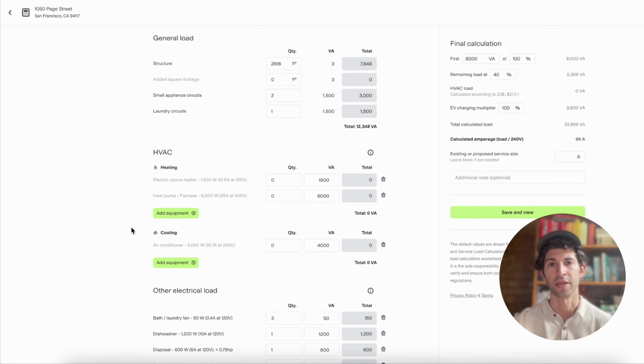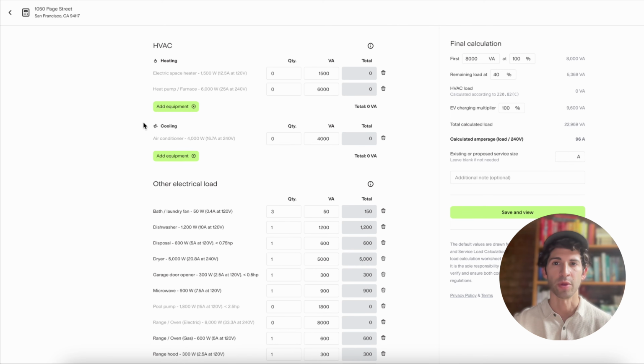Next, we can add in heating and cooling. The NEC says that when you have both a heating and a cooling system, you only need to include the larger of the 2 loads, not both. If you have equipment that is involved in both the heating and cooling scenarios, like a heat pump, put it in both the heating load and the cooling load section, and the software will automatically pick the larger load.